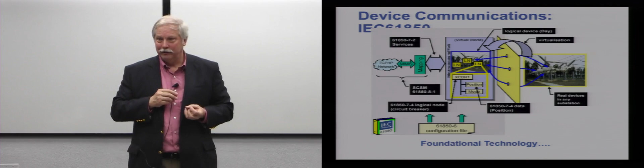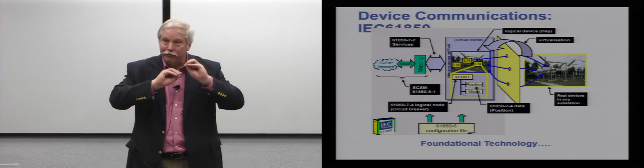In 61850, we have services also. What do I want to do with the data? I want to get the data, and in fact, get data is the actual name of the service in 61850. If I want to put settings into a device, I want to put data. Let's say I've captured a file for oscillography, I want to get file. If I want to put settings in for the whole relay, I put file, which is the settings for the entire relay. So 61850 consists of data models and services to access and work with those data models.